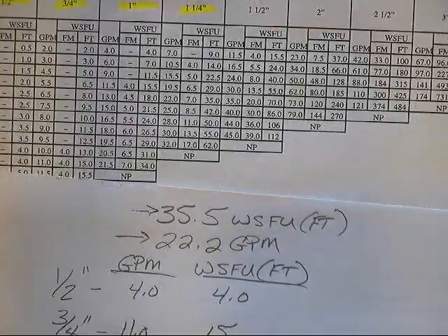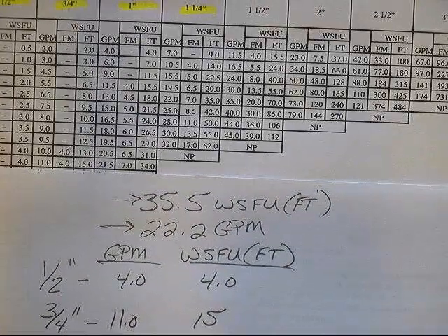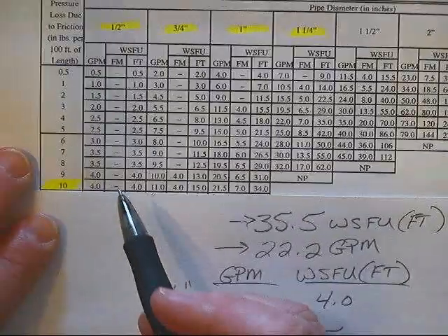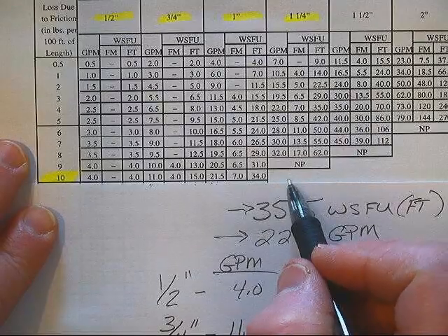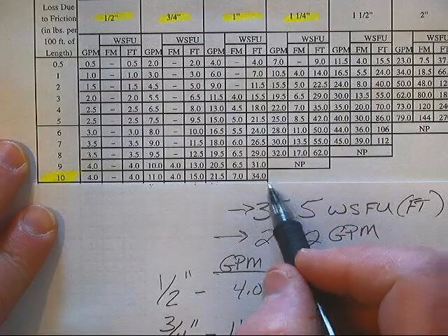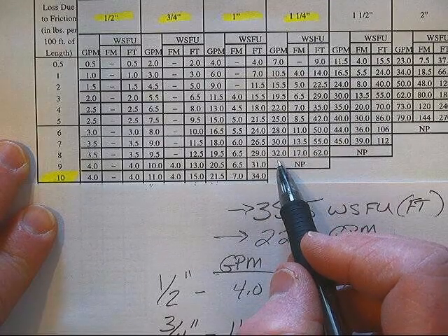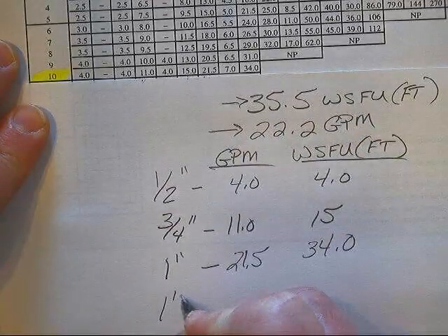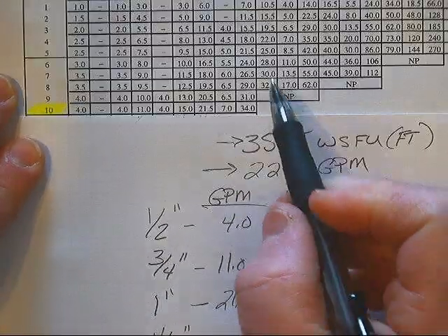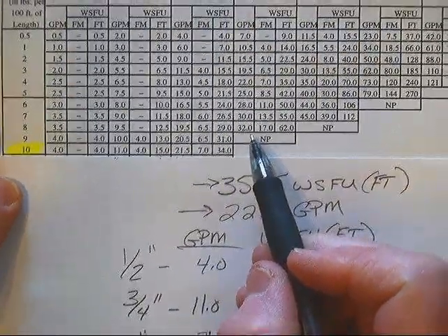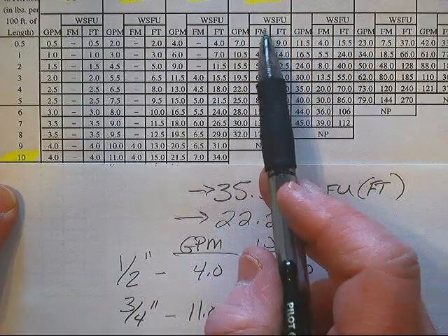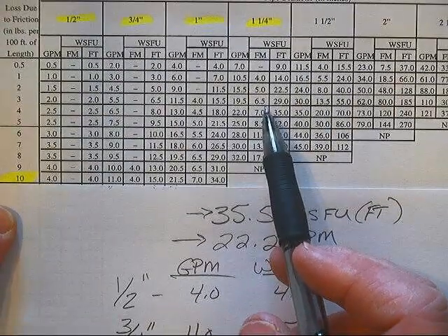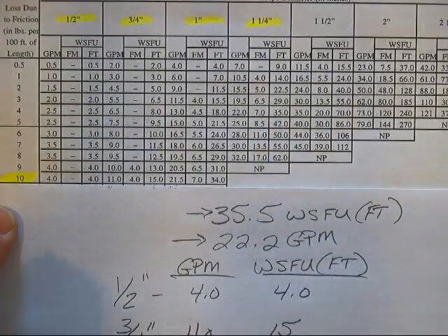So we simply go back to our A value, which was 10, and we read up, if you will. We jump up. This right here on 1.25" pipe, this is the maximum GPM and WSFU that I can put on that given pipe and not exceed 8 feet per second.